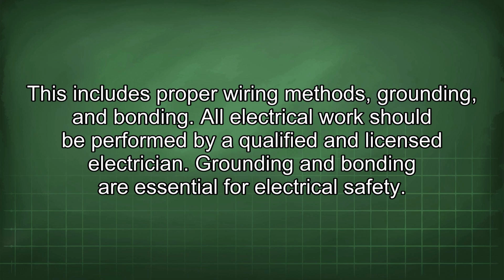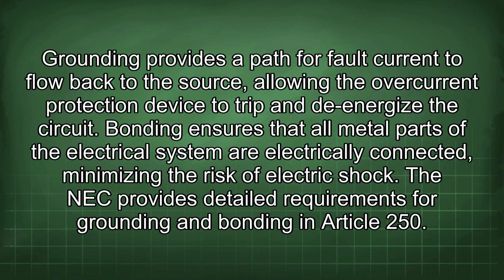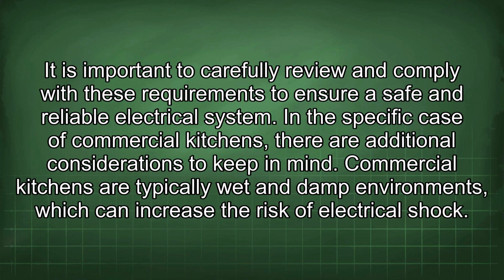Grounding and bonding are essential for electrical safety. Grounding provides a path for fault current to flow back to the source, allowing the overcurrent protection device to trip and de-energize the circuit. Bonding ensures that all metal parts of the electrical system are electrically connected, minimizing the risk of electric shock. The NEC provides detailed requirements for grounding and bonding in Article 250. It is important to carefully review and comply with these requirements to ensure a safe and reliable electrical system.